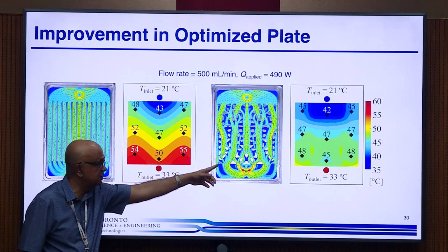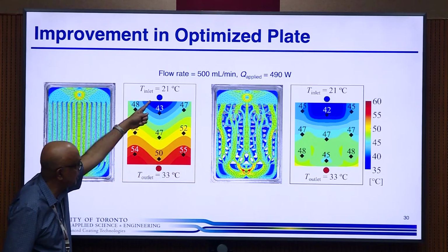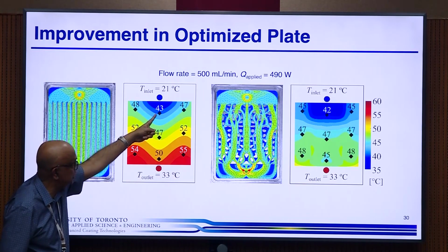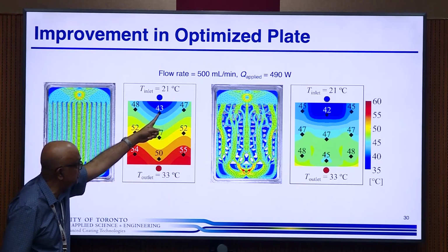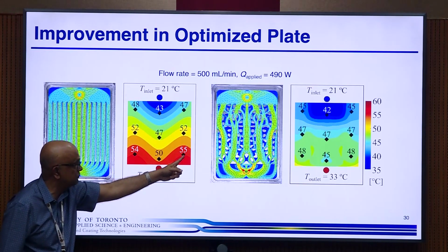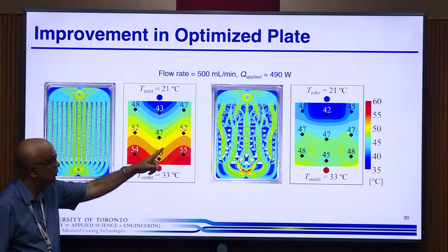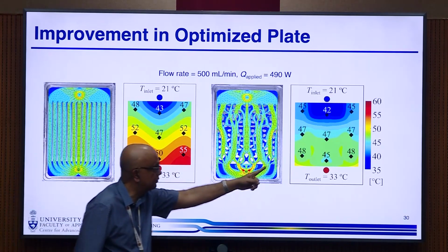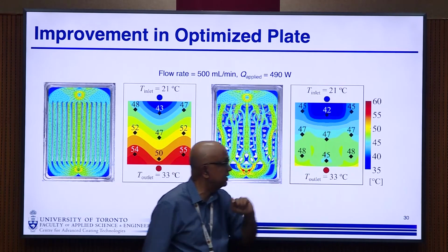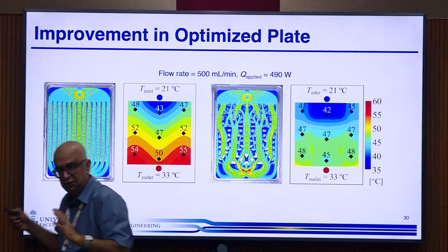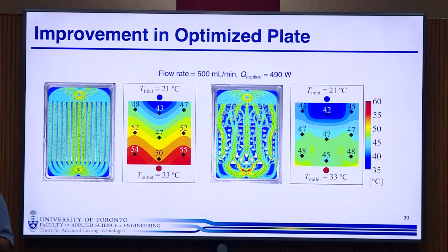This is optimized, so the water is coming in at 21. With the standard heat sink, the temperature varies from 43 all the way to 55. With the optimized one, we're going from 42 just to 48, so we've reduced the temperature difference significantly.